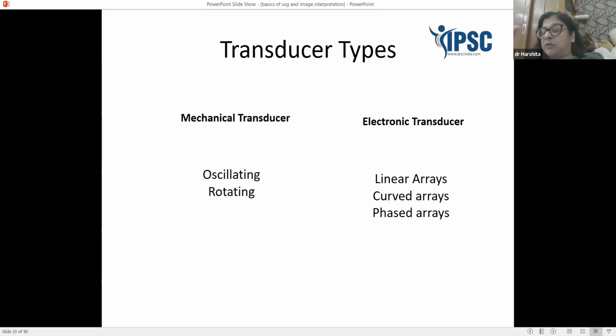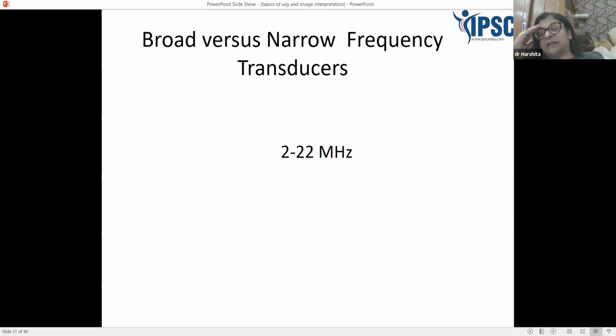So electronic transducers are more sturdy and they don't break easily as compared to the mechanical transducers. But still, we have got a combination of mechanical and electronic transducers in 3D and 4D probes because we need a multi-dimensional view. If one of you has seen a 3D probe or a 4D probe, you can feel the machine moving within it. That is the mechanical probe, but it has also got an electronic transducer within. So now the transducers are of various frequency. They can vary from 2 to 20 megahertz. Now I told you earlier in the lecture that it is the frequency which decides the penetration and the resolution. So will a 2 megahertz probe have a better penetration or a better resolution?